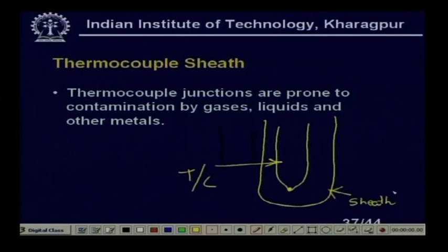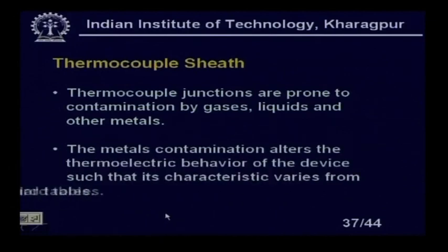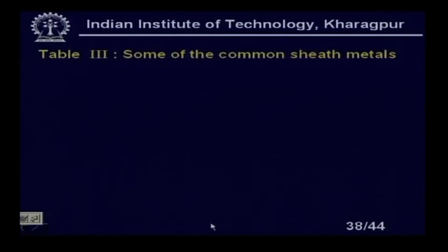Right. So, obviously, it will protect your thermocouple from any hostile environment, suppose any corrosion of that type, but it will increase the time constant of the system. Metal contamination alters the thermoelectric behavior of the device such that its characteristics vary from those published in standard tables. Because the calibration changes, everything will be changed.